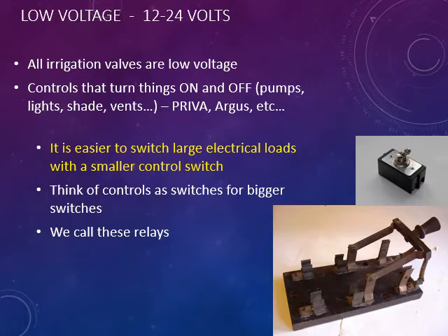The other area where we see low voltage is in what we call controls. So I've already mentioned irrigation valves. Those valves, the timer like I showed earlier, will send out a 24 volt AC voltage to the valve, which then opens it and lets water flow. The Priva or Argus or whatever computer usually runs a 24 volt alternating current or AC supply out to the valve to open and close it, as an example. Now, the other things that Privas control, like shade curtains, motors that open vents, circulating fans, even turning boilers on, they're also all switched by 24 volt AC circuits.